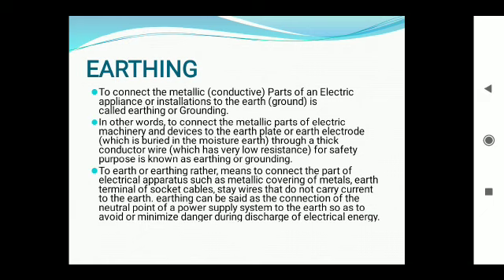And earthing can also be said as the connection of the neutral point of a power supply system to the earth so as to avoid or minimize the danger during discharge of electrical energy. And this is known as the system earthing. So there are two types of earthing. One is system earthing, another is equipment earthing.